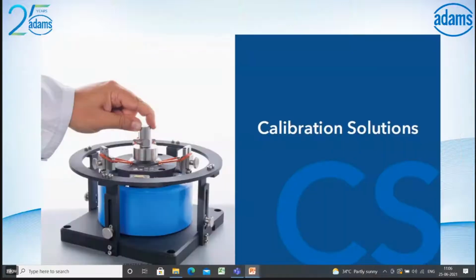For calibration solutions, Spectra offers both primary and secondary calibration. Primary calibration is an absolute calibration method for vibration and shock, where the excitation axis is traced back to the wavelength of helium-neon laser light by the laser interferometry method. Secondary calibration is for reference standard accelerometer calibration, and it is a comparison calibration method. The calibration is done by comparing the test object with the reference standard, so the unknown transfer coefficient of a test object is traced to the known transfer coefficient of a reference standard.